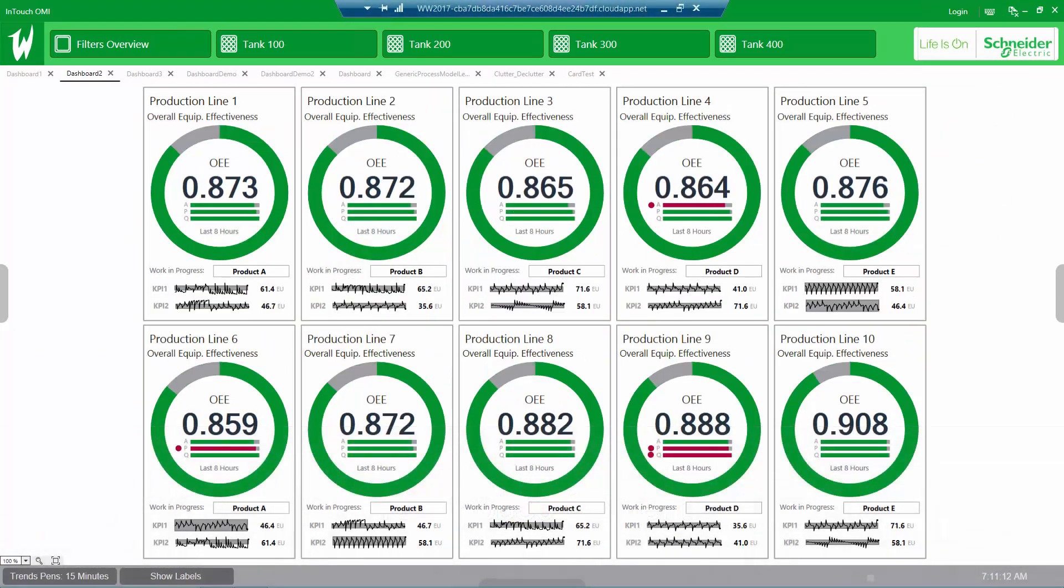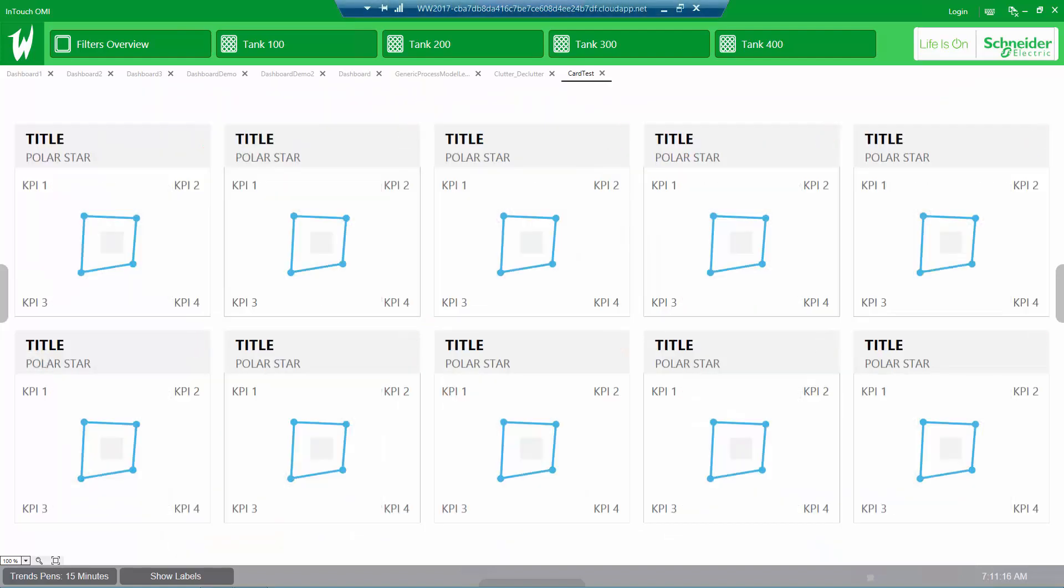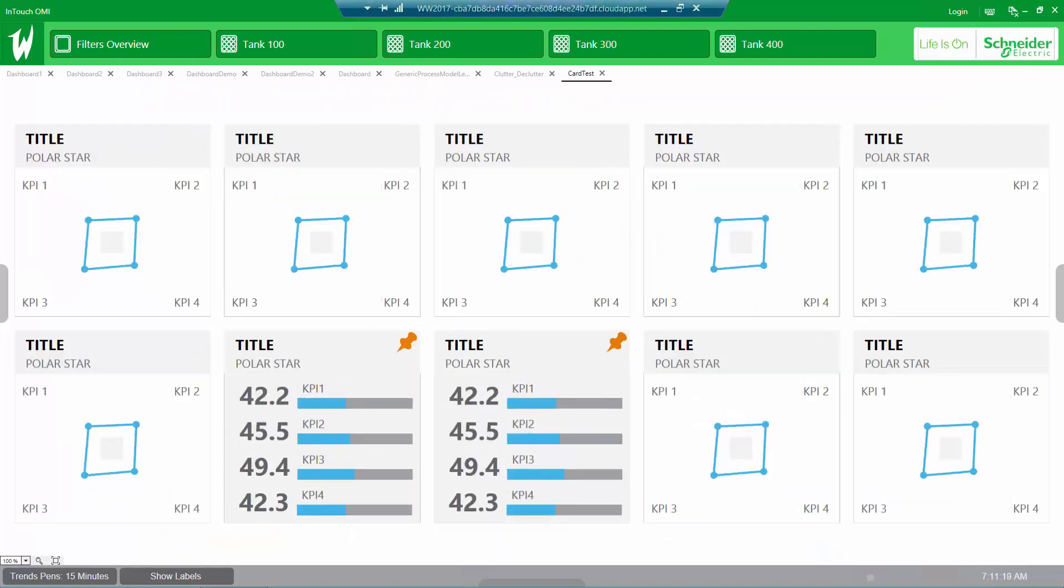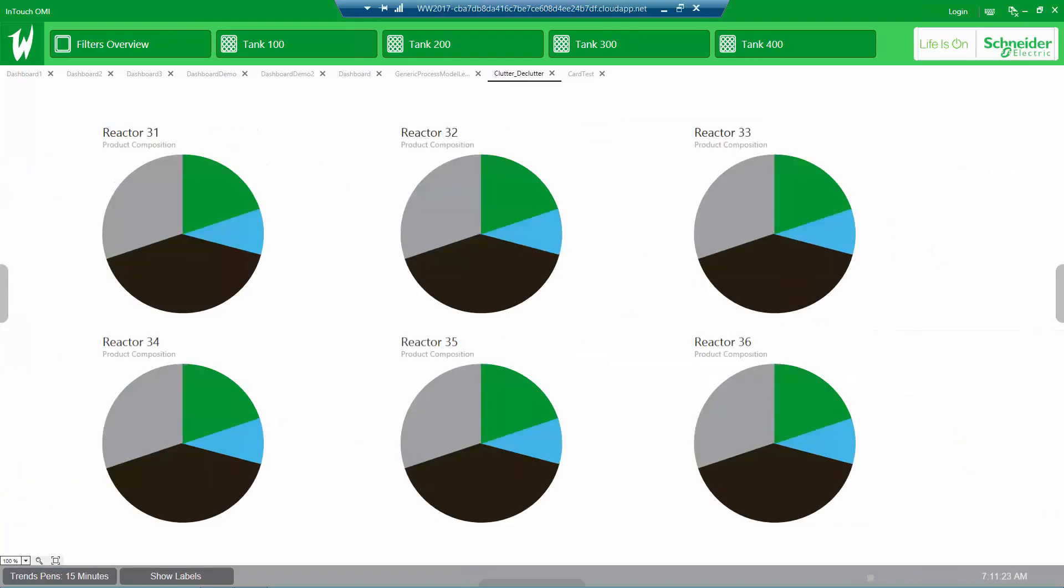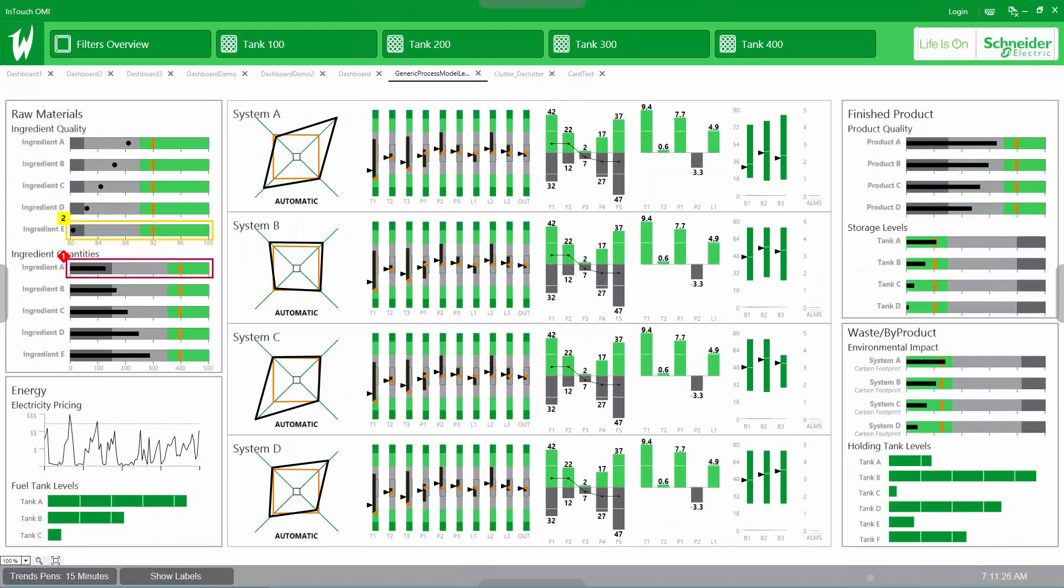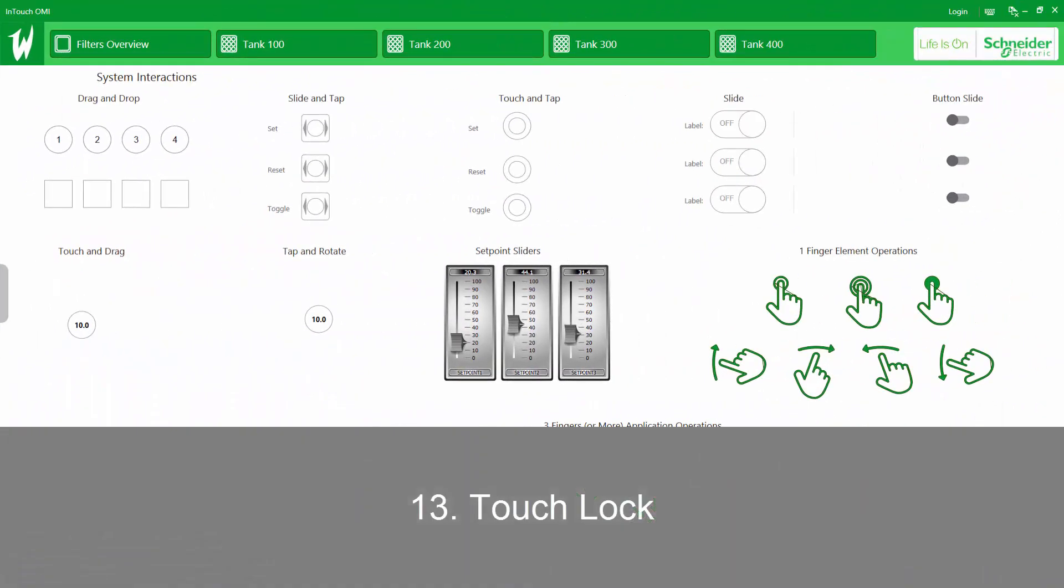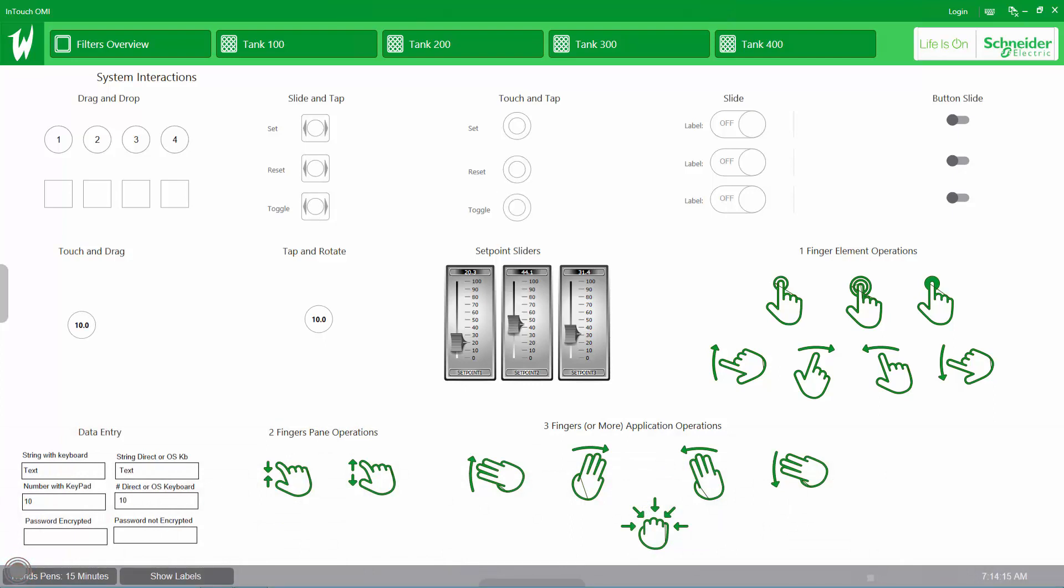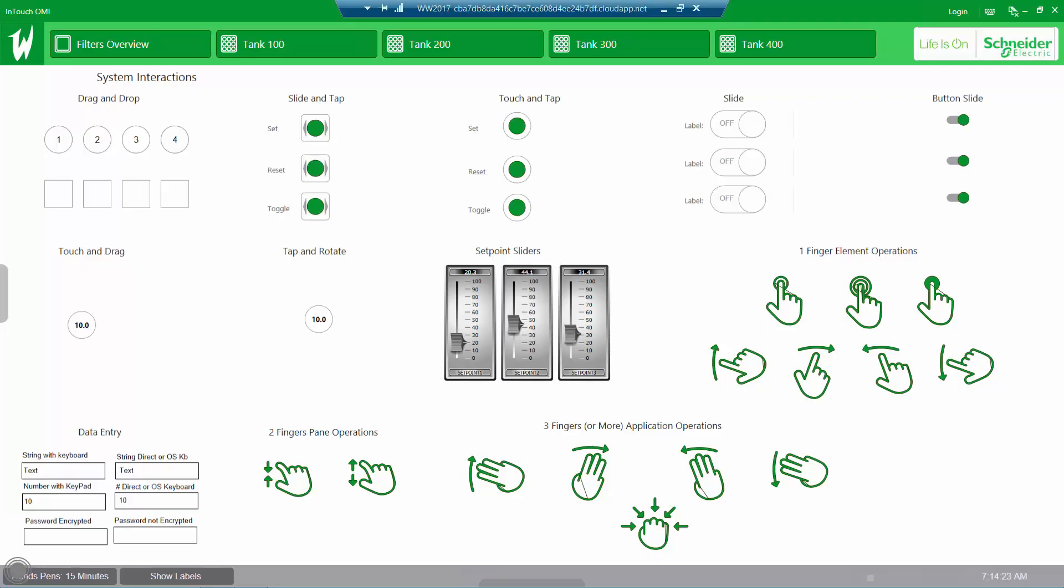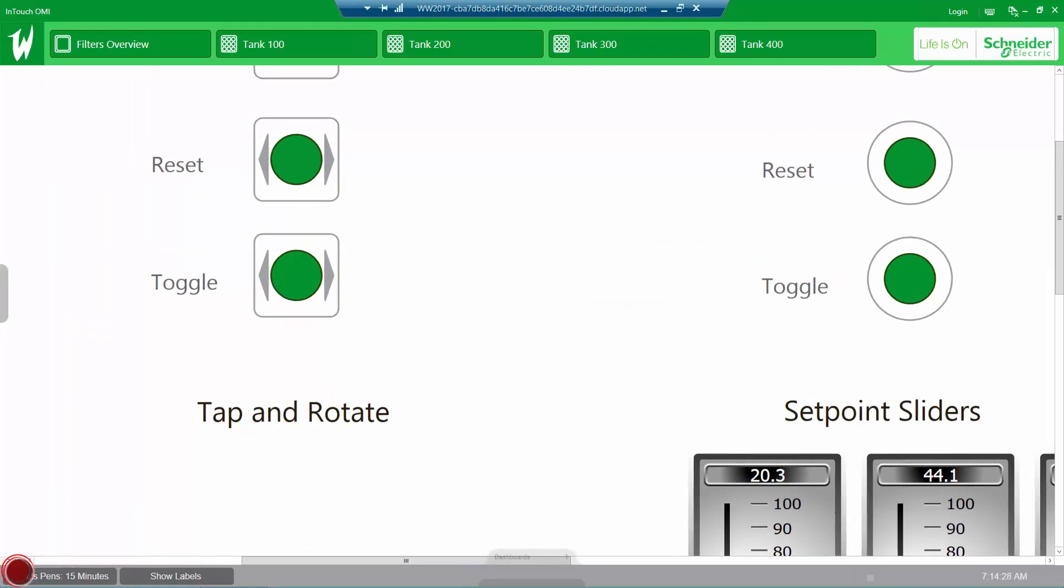When your navigation model has a number of graphics to display, a pane in the layout can be set to automatically tab that content. You can navigate those tabs directly or swipe across the content to switch tabs. In many industrial processes, you may want to ensure the operator has their hands away from the equipment or prevent unintended actions from errant screen touches. The touch lock mechanism will allow simple navigation touches while preventing commands until the touch lock button is pressed simultaneously.